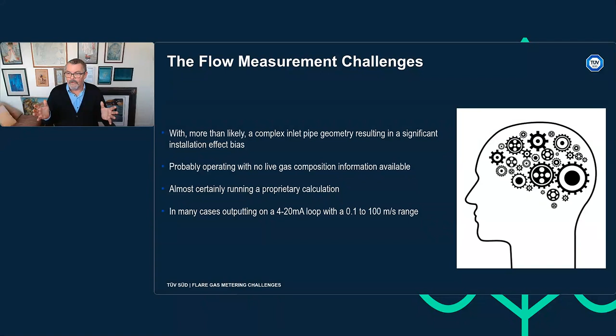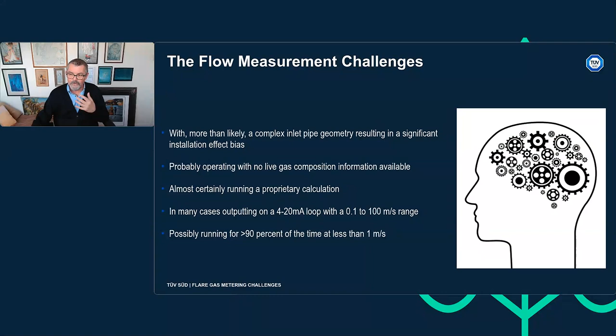And in many cases, for the older systems, the 20-year-old, 25-year-old, 30-year-old flares, we're talking pre-digital communications for a lot of these installations. So they're probably using a 4 to 20 milliamp output and an analog input at the DCS or the flow computer. And it's probably got a very large range to cover the operating range of the flare. So in that case, they're at a 1,000 to 1 turn down ratio. And possibly, as we move into a low flaring landscape, it's running for the vast majority of the time at very, very low flow rates. And that's a challenge from a measurement perspective.